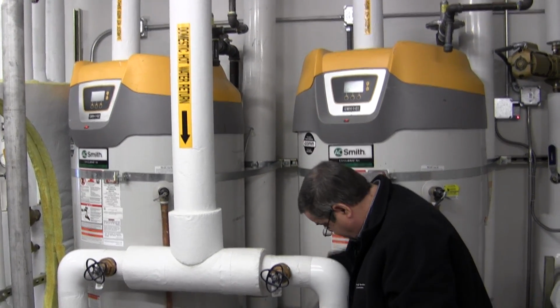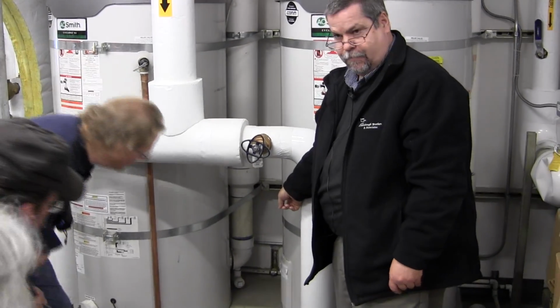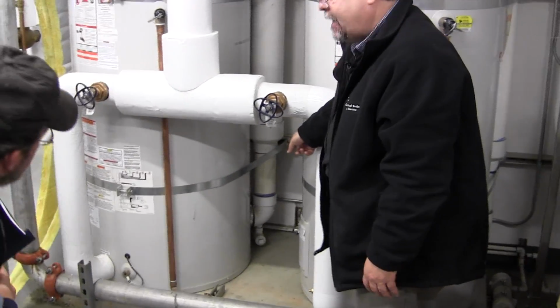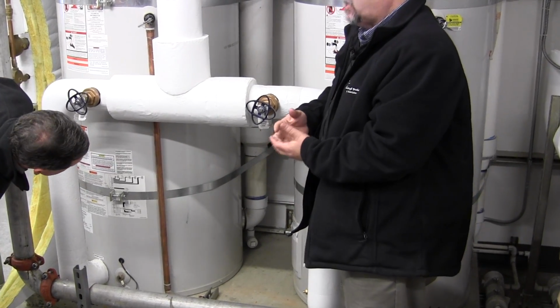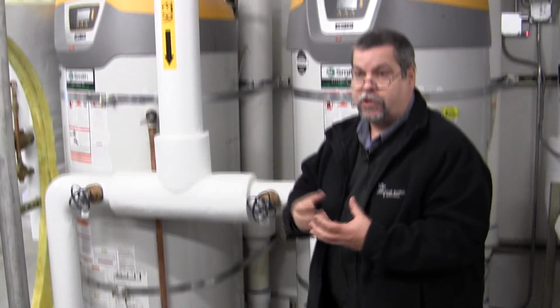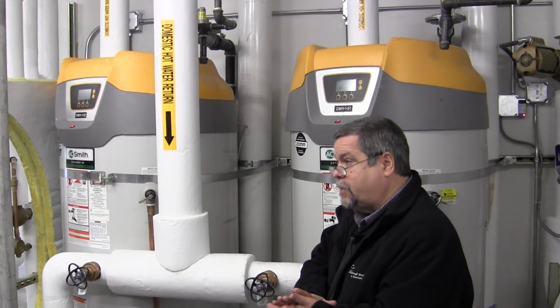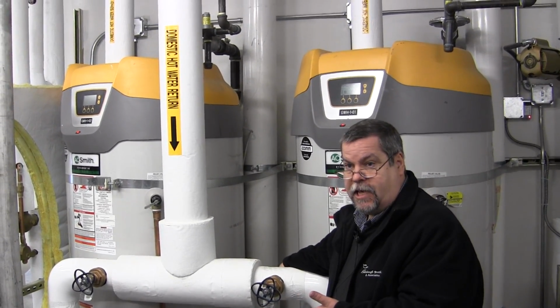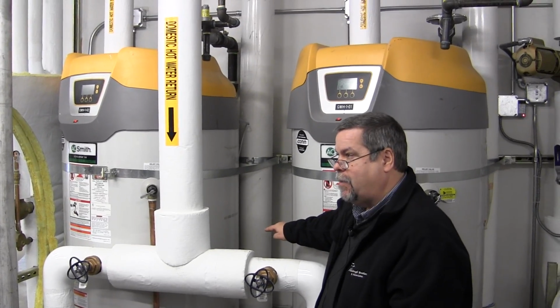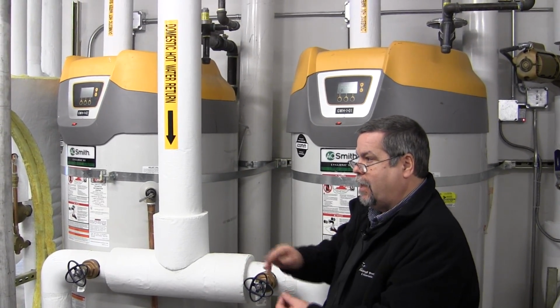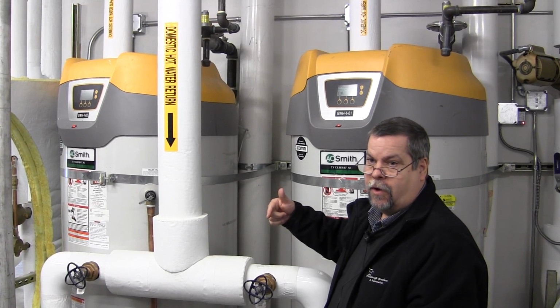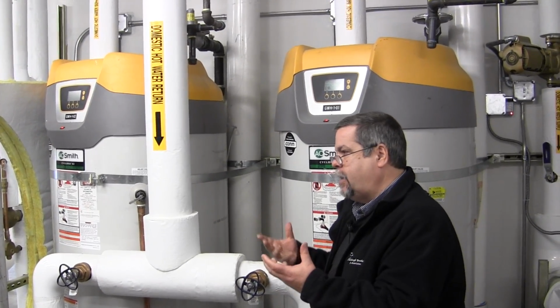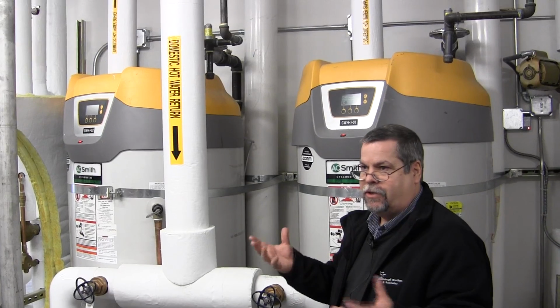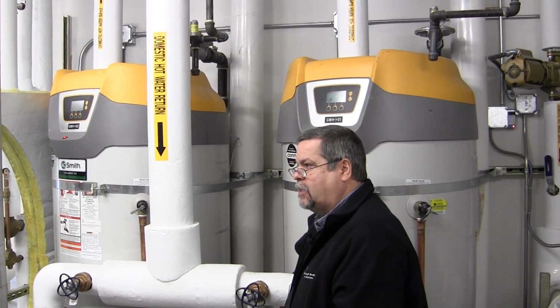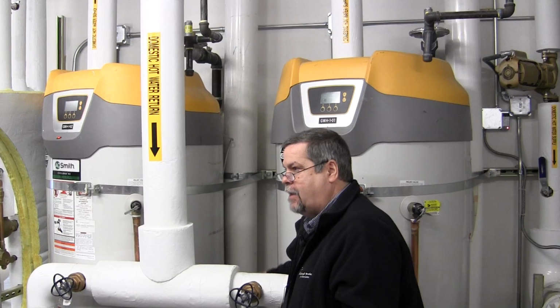Does everyone see this little clean out T down there? Imagine if that clean out T was to somehow get clogged up, because these units are 96% efficient, so they make a lot of condensate. So if the condensate could not drain out through that T, the condensate would start filling up this pipe. And once it gets to a certain level in that pipe, it's going to say block flue, it's going to shut your unit down. So, depending on how long it's been running and what can get in there during construction or long term, that's a key maintenance point there. A lot of times if it's block flue, you just drain that, and some PVC shavings will come out, and off you go.